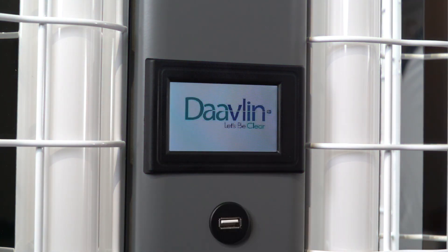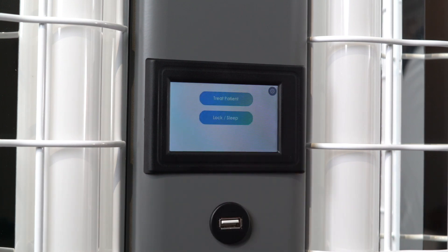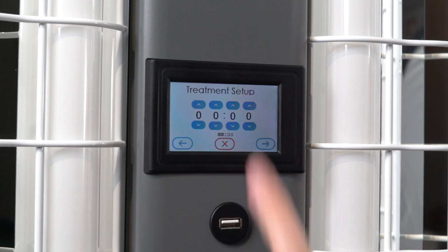To begin, touch the screen to awaken the unit. The Daavlin logo will appear—tap it. A numeric keypad will then appear. Enter your unlocking PIN code followed by the arrow key. Next, press the Treat Patient button.